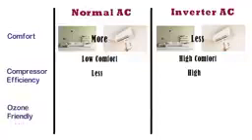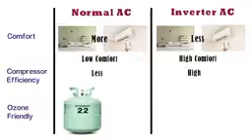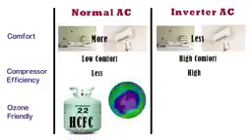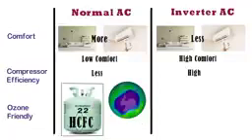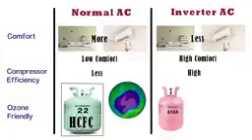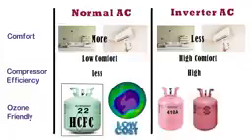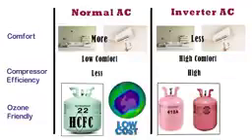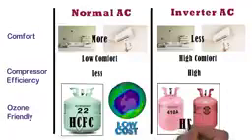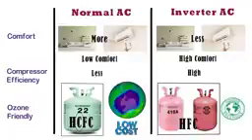Ozone friendly: Most normal air conditioners use R22 refrigerant, which contains HCFC — hydrochlorofluorocarbon — an additional chlorine component that destroys the ozone layer. Always enquire about the refrigerant used, as some installers prefer R22 since it is cheaper compared to R410A or R32. Most inverter ACs use R410A or R32 refrigerants, which are ozone friendly, as these contain only HFC — hydrofluorocarbon.